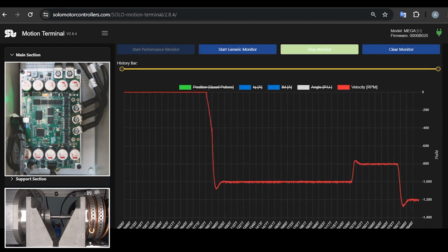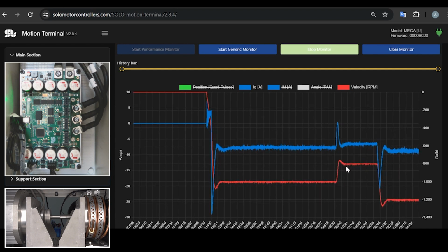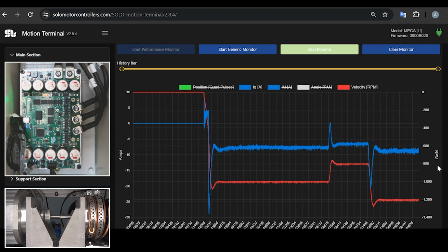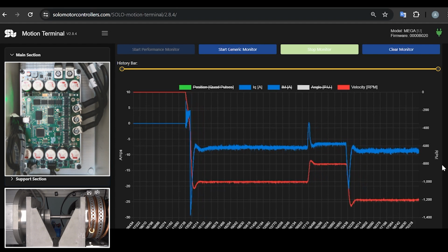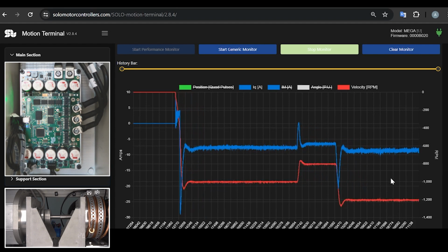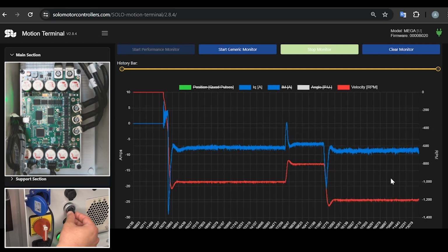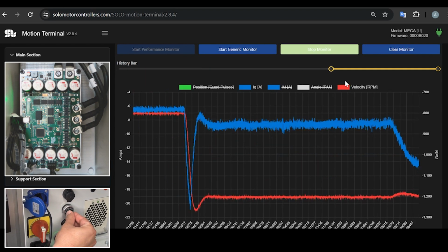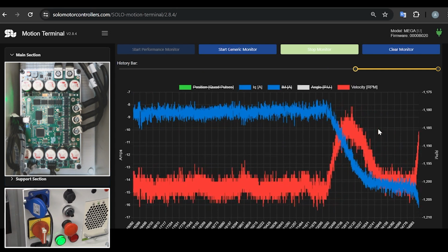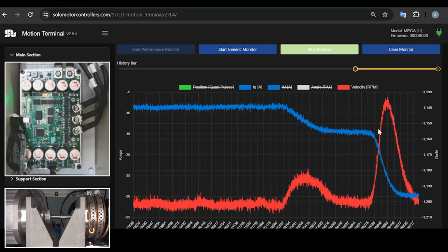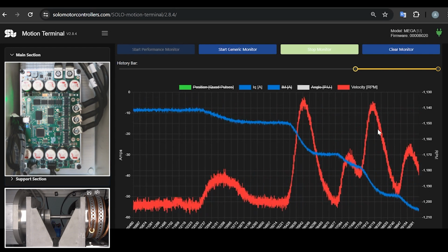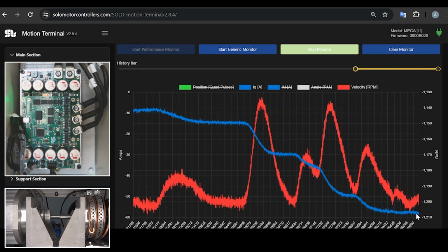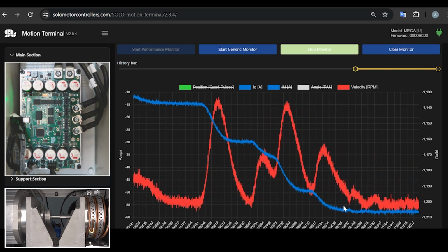The motor is at 1200 RPM now, and the torque is not that much. So we have a very low current consumption for this type of motor. Now in this system, we have a powder brake that I just showed you. I can increase the torque on the shaft of the motor. If I increase the current a little bit and zoom in, you can see the current is now rising. I can go all the way up to 50 or 60 amps. Yes, 60 amps now in the motor, and the speed is at 1200 as we said before.